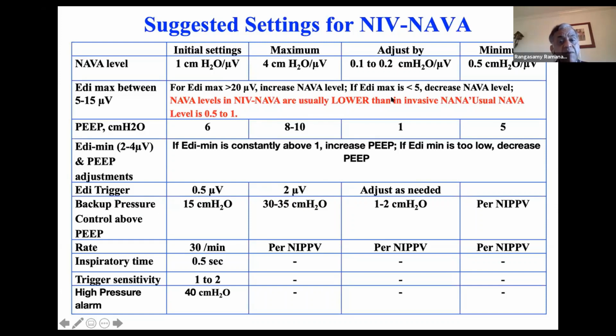Backup pressure. This is in case the baby totally becomes apneic, no respiratory drive, then you have to have backup pressure ventilation. It's a pressure controlled mode on the NAVA machine. So you set 15 PIP, 15/5. Maximum use 30 to 35. Rate, usually don't need more than 30. I time for the backup rate is 0.5 seconds. Trigger sensitivity, they have it as number 1 or 2. You start with 1 to see how the baby does. High pressure alarm, you set it at 40 centimeters.